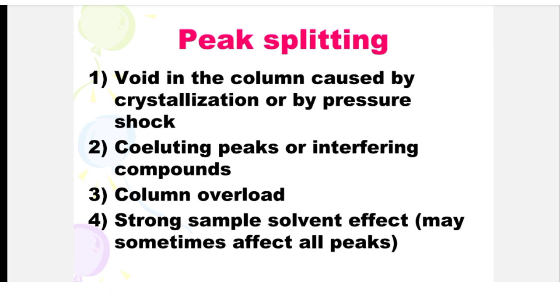Next is peak splitting. Peak splitting is due to damage in the column caused by crystallization or by pressure shock, coeluting peaks or interfering compounds, column overload, and strong sample solvent effect.